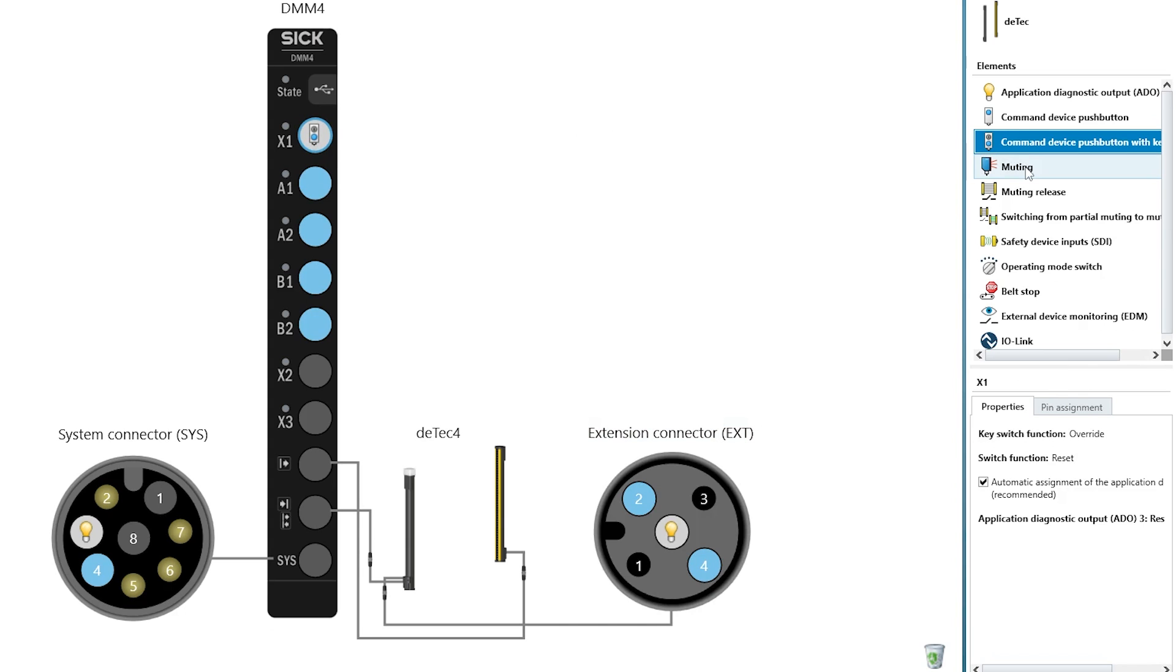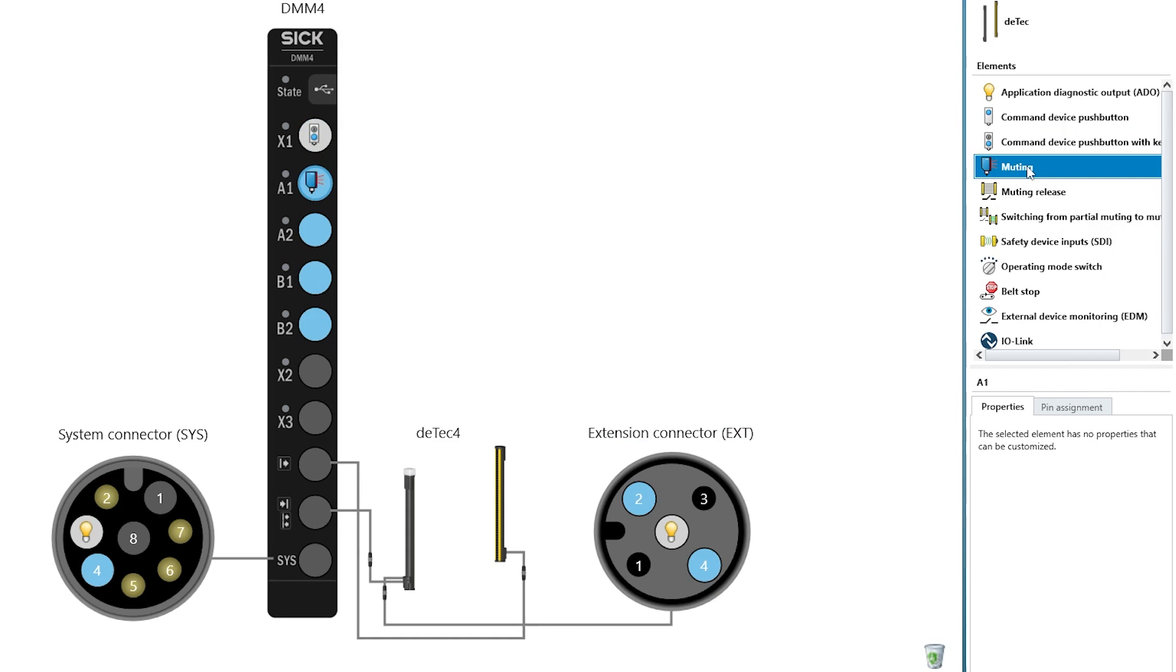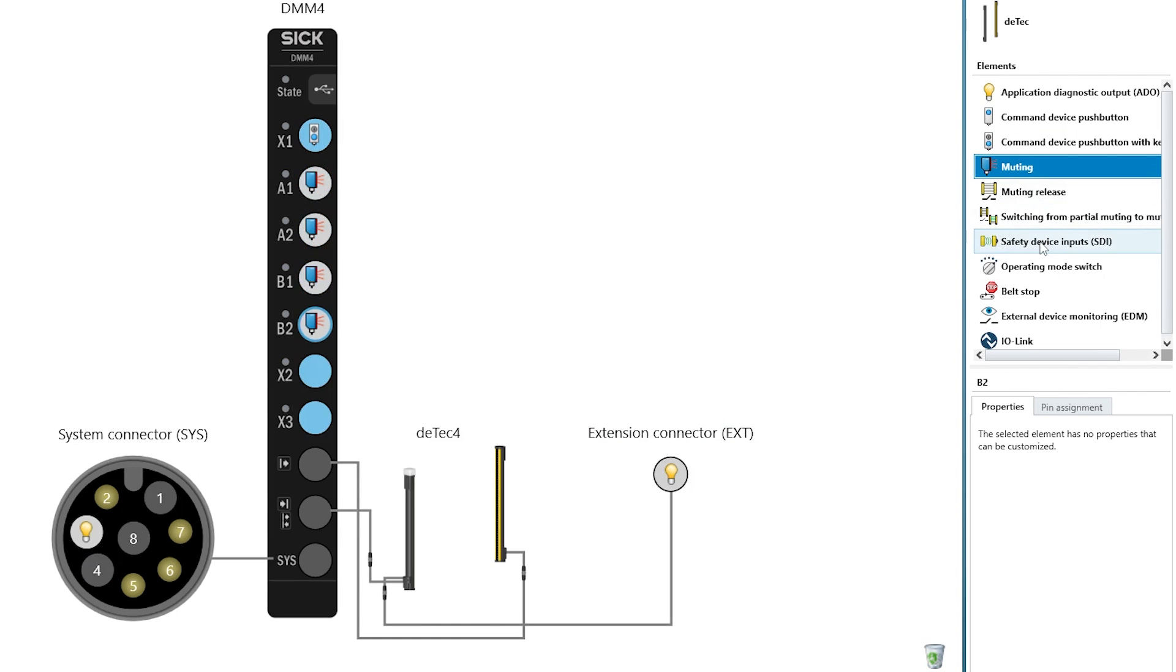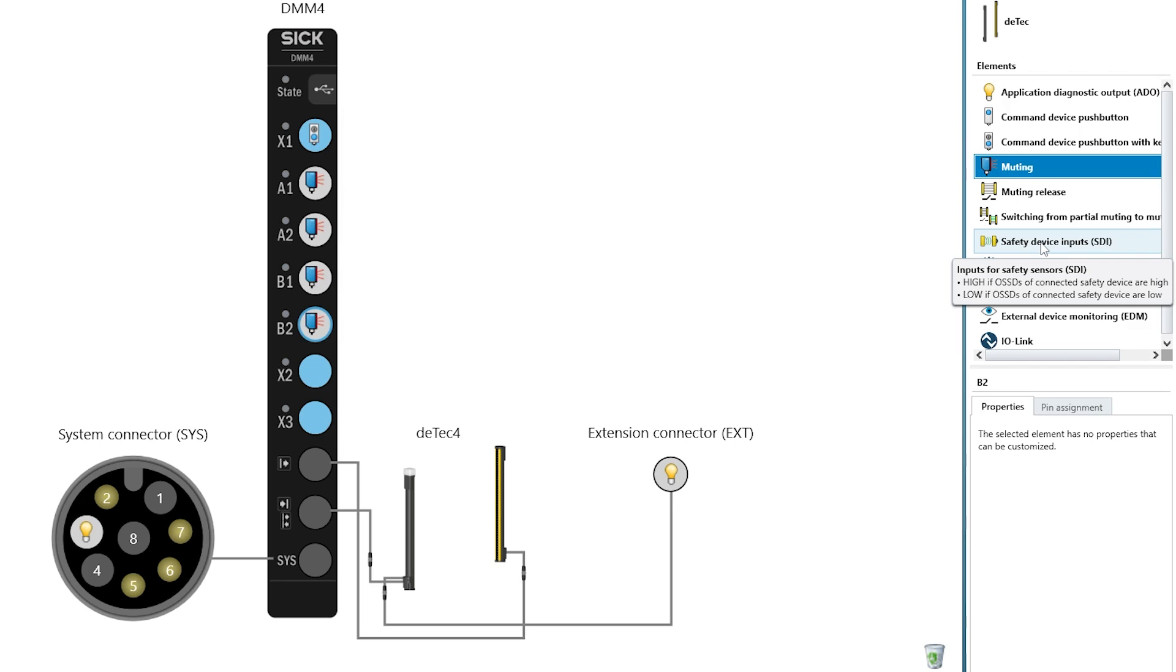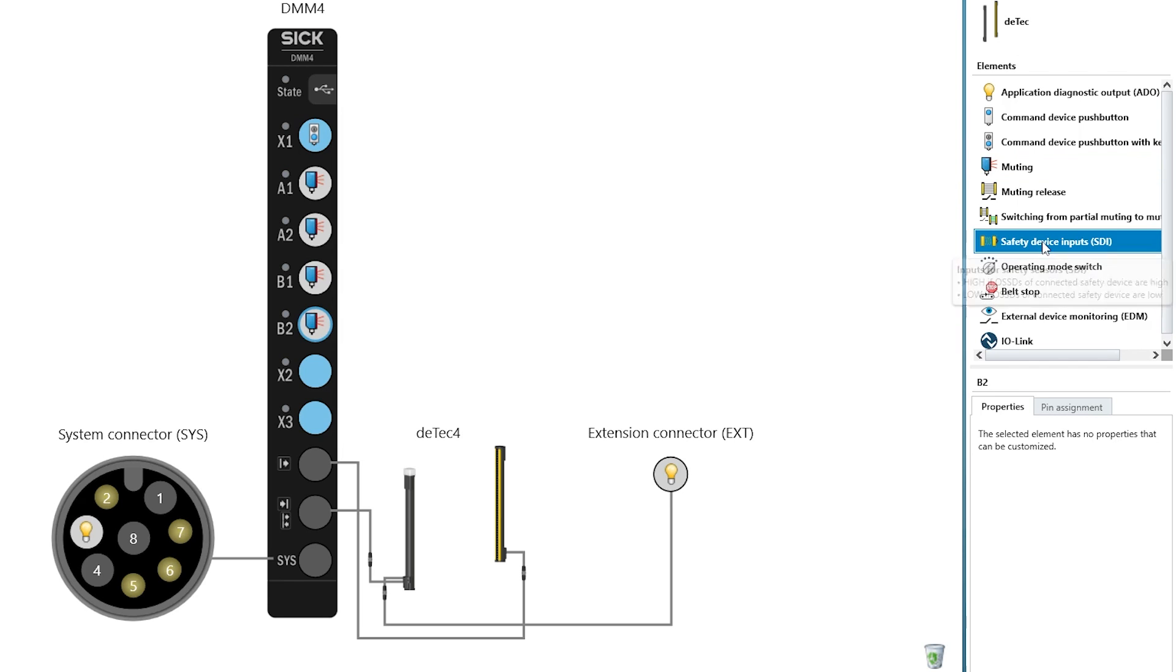Now you assign the four muting sensors to the four inputs marked in blue. If you want to connect a safety device, which for example safeguards a door in the muting station, you can connect it directly to DMM4 to save cabling. The Safety Designer shows three connection options in blue. In our case, we select X2.